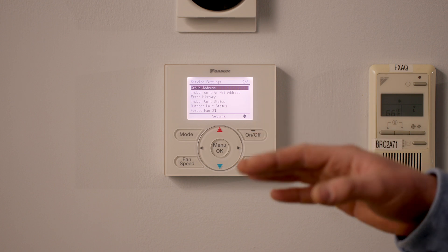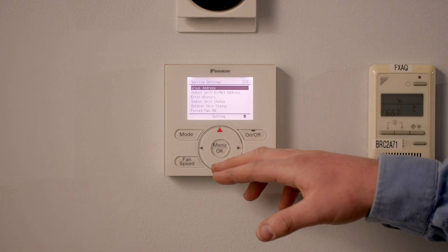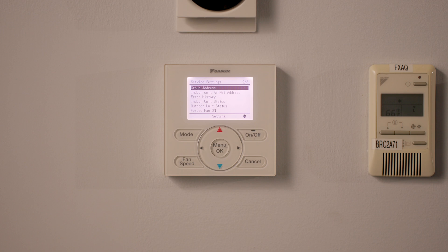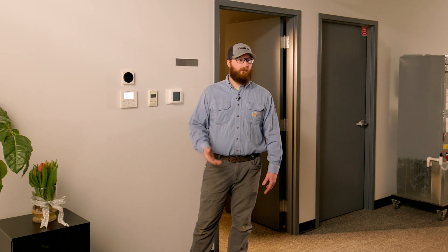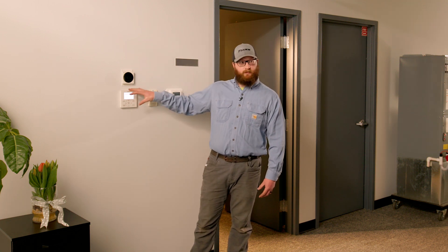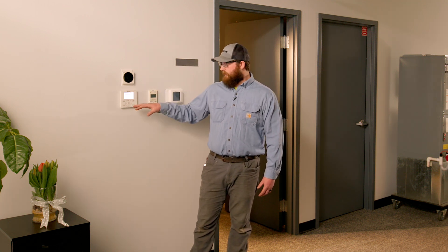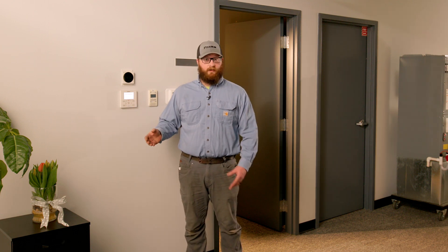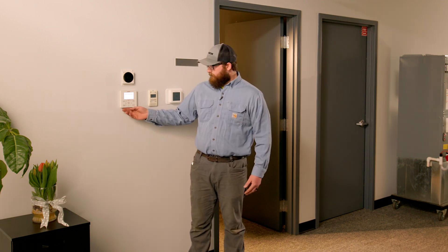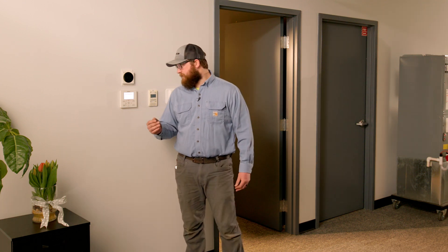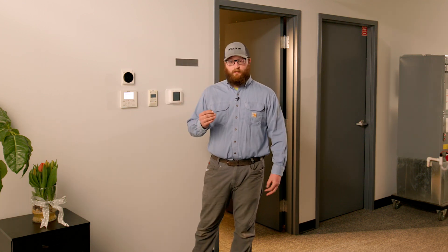Another important one on commissioning is going to be group addressing and indoor unit AirNet addressing. That's important because when we start up and commission a building, we'll have anywhere from five to 800 indoor units. Each of them can have their own individual control like this, and each of them also have to have a specific address — i.e., a name — to go to it. So when we pull it into an iTouch controller, we know what unit that is.